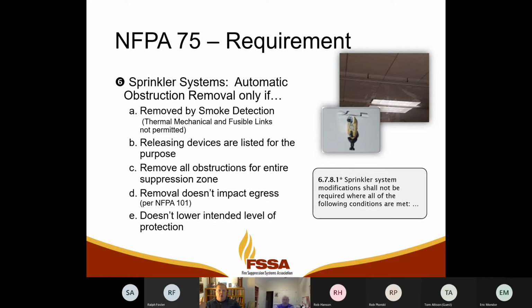Okay, the system must be removed by smoke detection. So fusible links, thermal detectors are not allowed. It has to be removed by smoke detection early in the timeline of the fire. Second, releasing devices must be listed for the purpose. So, this device must be listed to release your obstruction in your system. So, there's some mismatches that can happen out there if you're just buying the same fusible links that you would be releasing roll up doors with, or roll down doors with, or fire doors with in other occupancies. So there, it's got to be listed for that purpose.